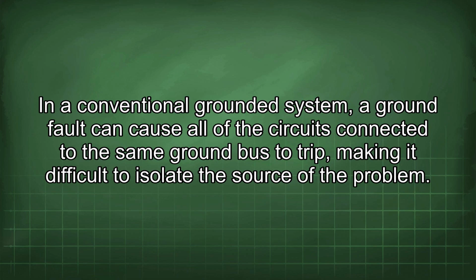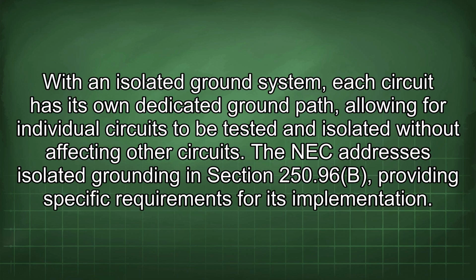In a conventional grounded system, a ground fault can cause all of the circuits connected to the same ground bus to trip, making it difficult to isolate the source of the problem. With an isolated ground system, each circuit has its own dedicated ground path, allowing for individual circuits to be tested and isolated without affecting other circuits.